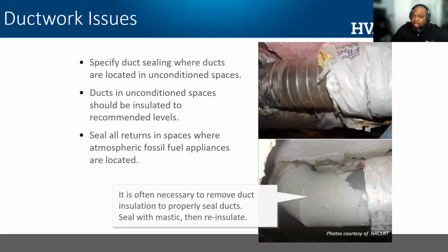All right. It helps us identify duct issues. If I didn't seal my ducts, remember duct issues, especially in an unconditioned space like a crawl space or attic, and on a return side, bring in particles, and that will also affect my temperatures. My temperature measurement can help me confirm that I do indeed have an IAQ problem.